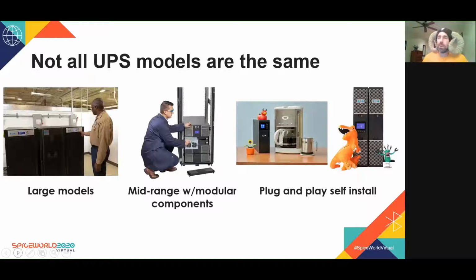Before I begin and turn it over to Sammy, I want to lay the groundwork a little. There are multiple types of UPSs. Some are very large, like the one on the left, about refrigerator size. Some can get really, really big, taking up an entire room, for the largest data centers. Most of the time, for Eaton, for the large UPSs, we require somebody to come in from Eaton and start up the UPS. And most often that's the best option going forward for preventive maintenance visits as well, so a couple times a year they come check everything out, batteries, connections, and make sure it's running properly. So it's really important to have a service plan for those.